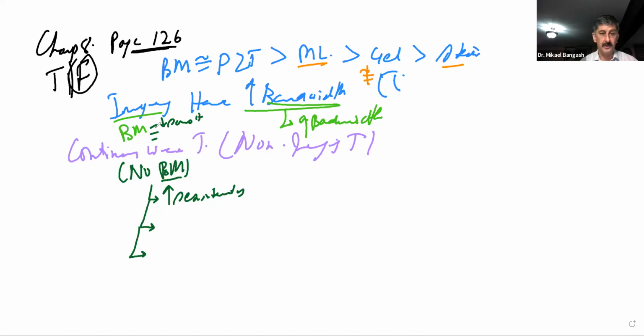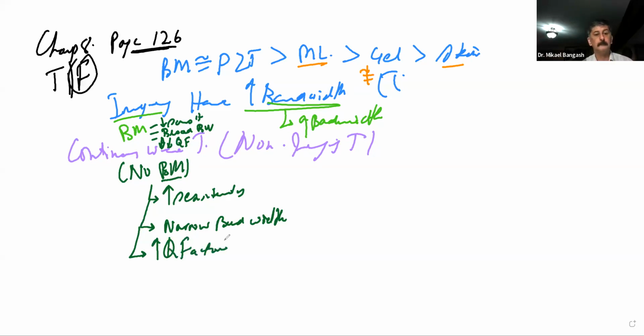Just like in an imaging transducer, we said that they have a broad bandwidth. But for your non-imaging transducer, or a transducer with no backing material, they will have a narrow bandwidth. Clear? And the last one, which was that they had a low quality factor, which was because of the broad bandwidth. Here you have a narrow bandwidth. That means you have a high quality factor.